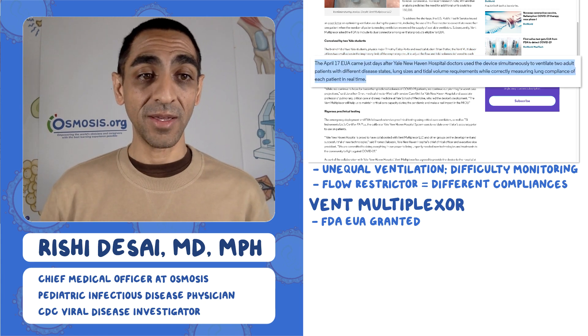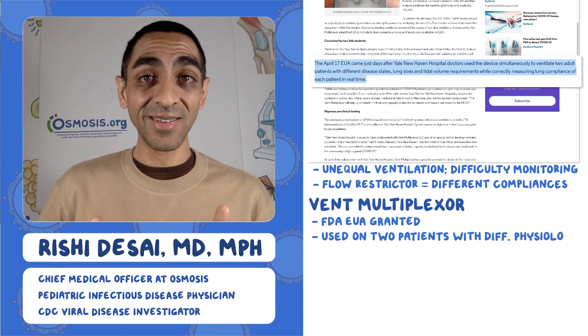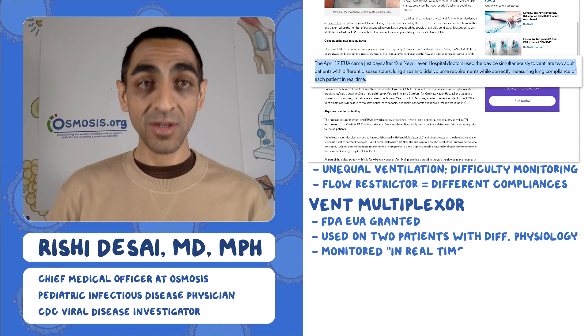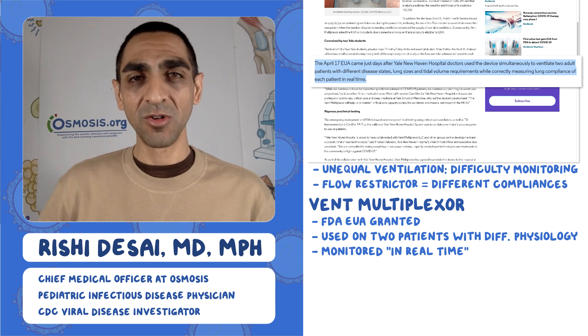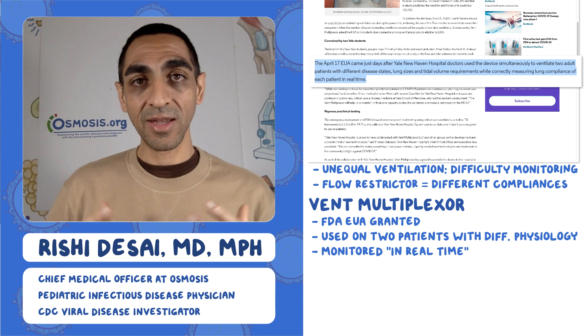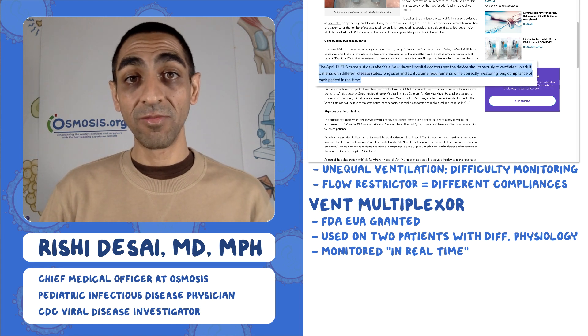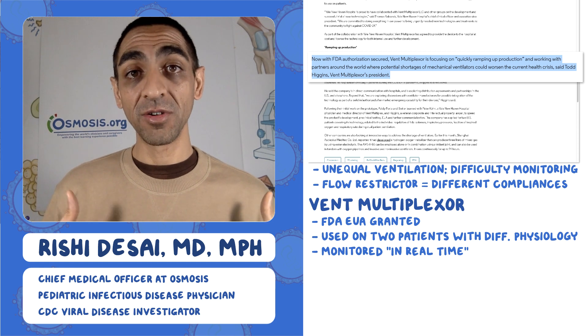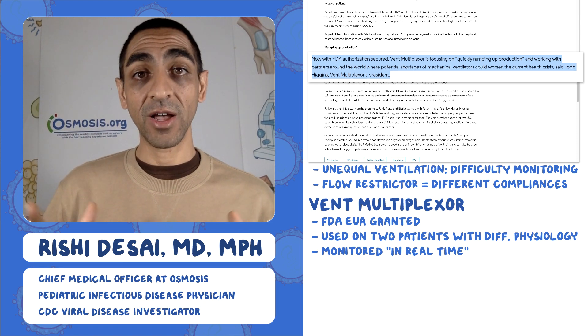What really impressed me: Yale New Haven doctors have used this device to ventilate two adult patients with different disease states. So no longer are we talking about simulations or mechanical lungs — these are real lungs hooked up to this device that have worked. These two adults had different disease states, which is really impressive because up until now it's been a very theoretical game. The FDA approved it — they just got emergency use authorization — meaning they're now free to ramp up production and help with ventilator shortfalls around the country and world.